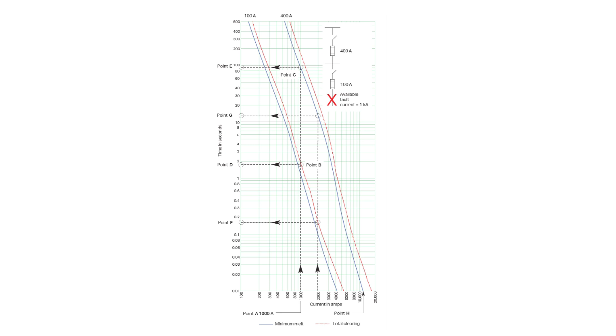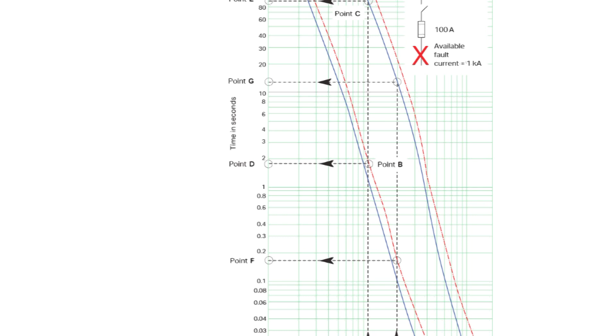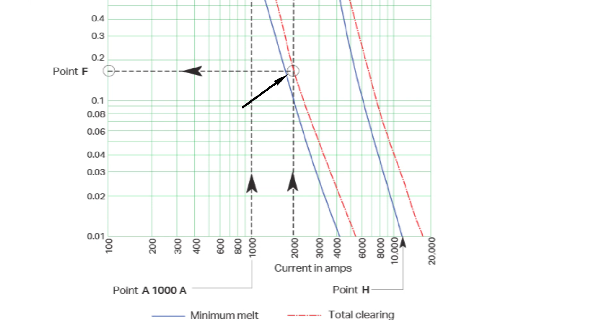approximately 200 seconds. However, for an overcurrent of 1000 amps, the 100 amp fuse will open in approximately 1.75 seconds, shown as point D. And for a 2000 amp overcurrent, the time current curve tells us it will open and clear in approximately 0.17 seconds. This will all be well before the time it takes the 400 amp fuse to even begin to melt.